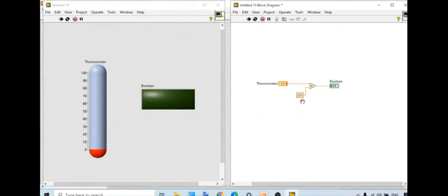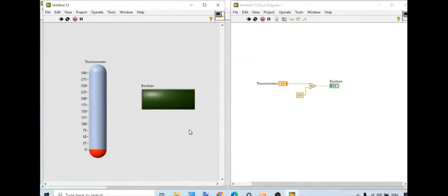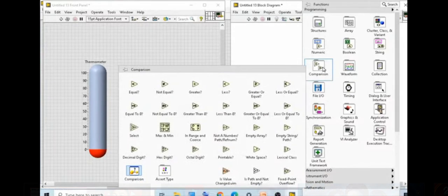And right now if you see this boiler, it's going about 225, and this thermometer can only measure from 0 to 100. That's going to be a problem. Rather, what I can do is I can change the thermometer output to 300. This thermometer can measure up to 300, okay, but your boiler may not be able to handle those things, because whenever you have something which can handle up to certain limit, the measurement system should be able to handle much more, right?